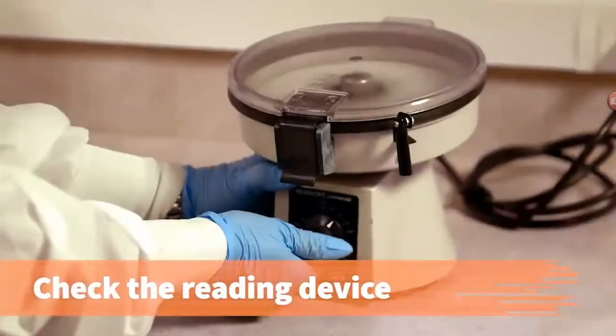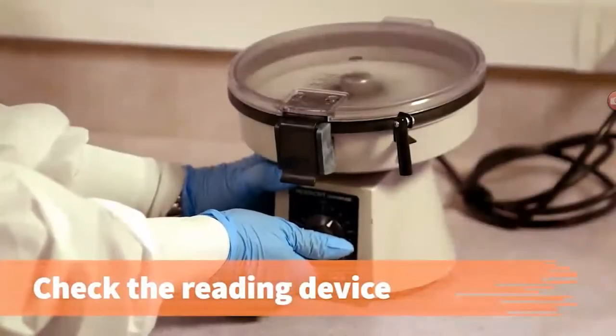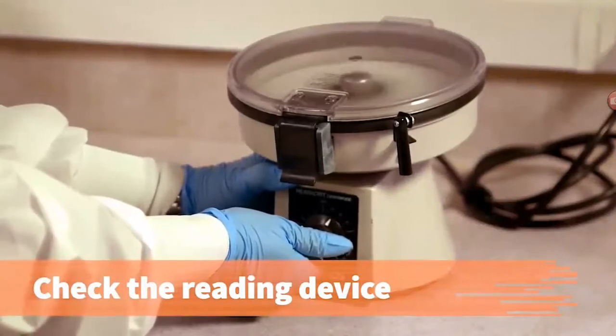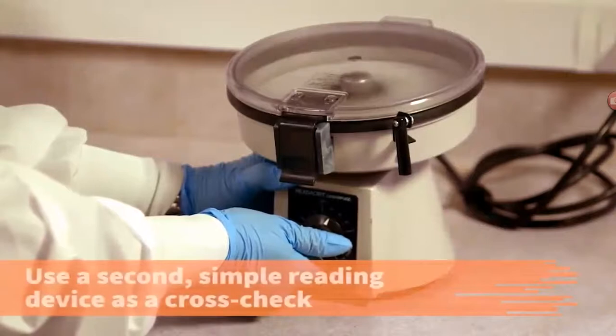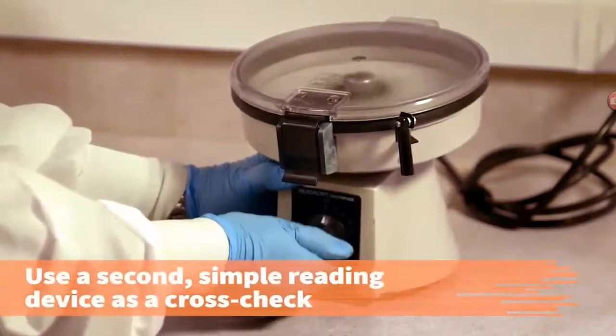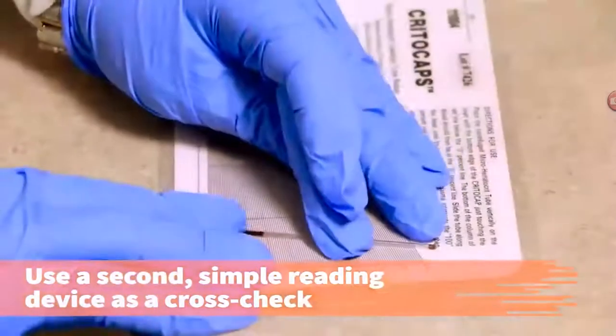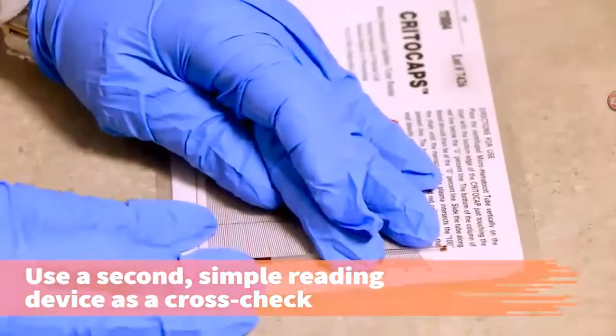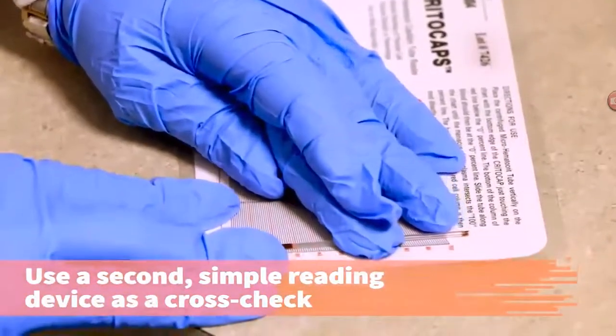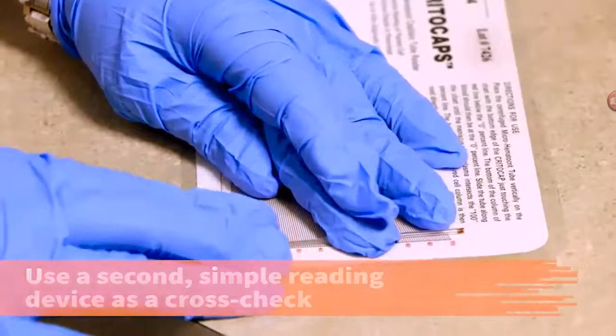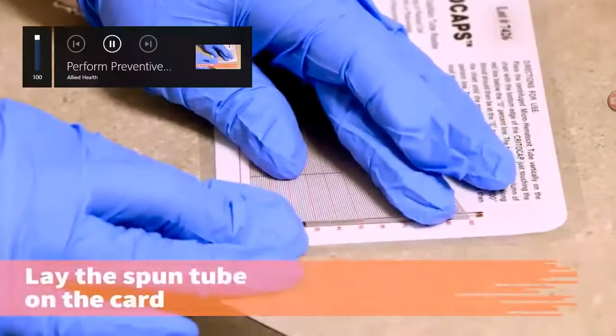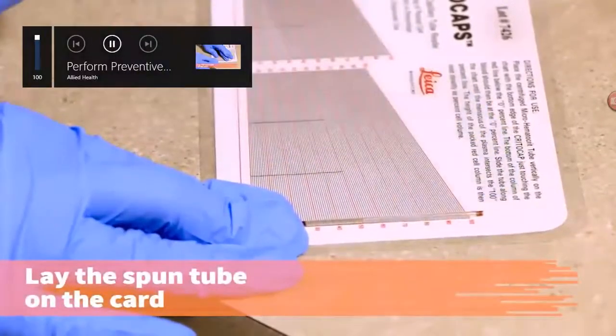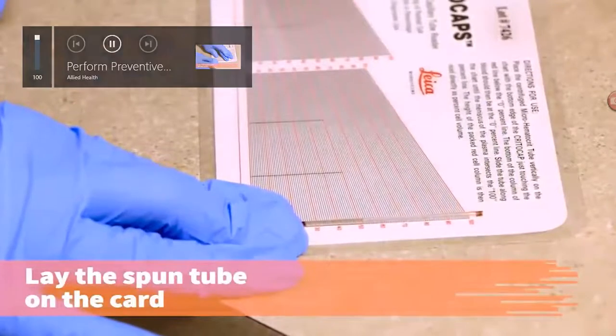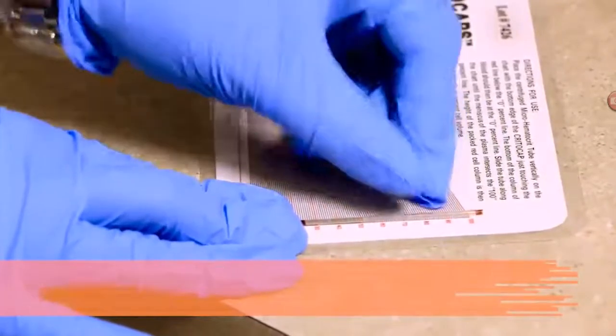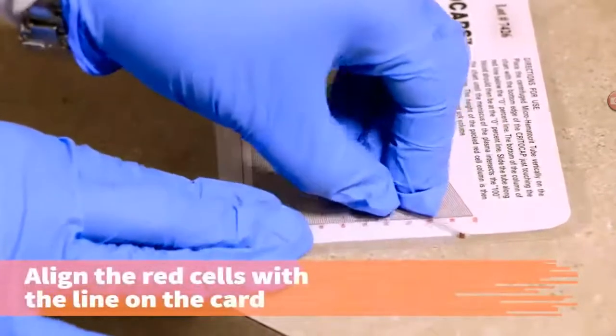Monthly, check the reading device. Misuse and zeroing of the reading devices can result in considerable error. Always use a second, simple reading device as a cross-check, such as a ruler or flat plastic card specifically made for this purpose. To use these cards, lay the spun hematocrit tube on the card and align the red cells with a line on the card to obtain the reading.